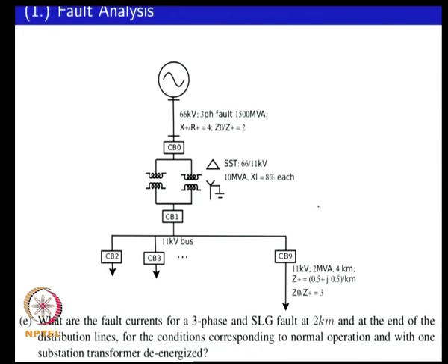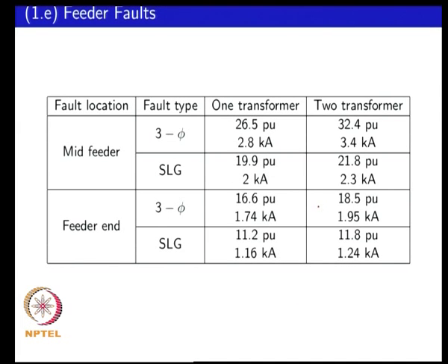The results are summarized in a table. As you go further away from the substation the fault current level is lower compared to what it was at the secondary side of the transformer, because you now have the added feeder impedance. The fault current level for the two-transformer case is higher — not double, but higher — than the single-transformer case. For faults at the end of the line, the single line-to-ground fault current is lower because the added feeder impedance is dominating and reduces the fault current level.